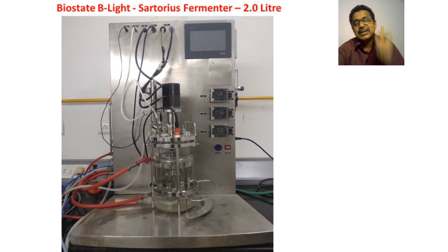So what does this machine do? It decides on its own at what time oxygen is to be supplied inside the machine. Inside the fermenter, one connection is to atmospheric air through an air pump, and the second is to an oxygen cylinder. The PID control itself decides when oxygen is to be pushed in, so your dissolved oxygen level is maintained. When dissolved oxygen level is maintained, your organism stays in healthy condition, and that is how it produces the product of your nutrition.